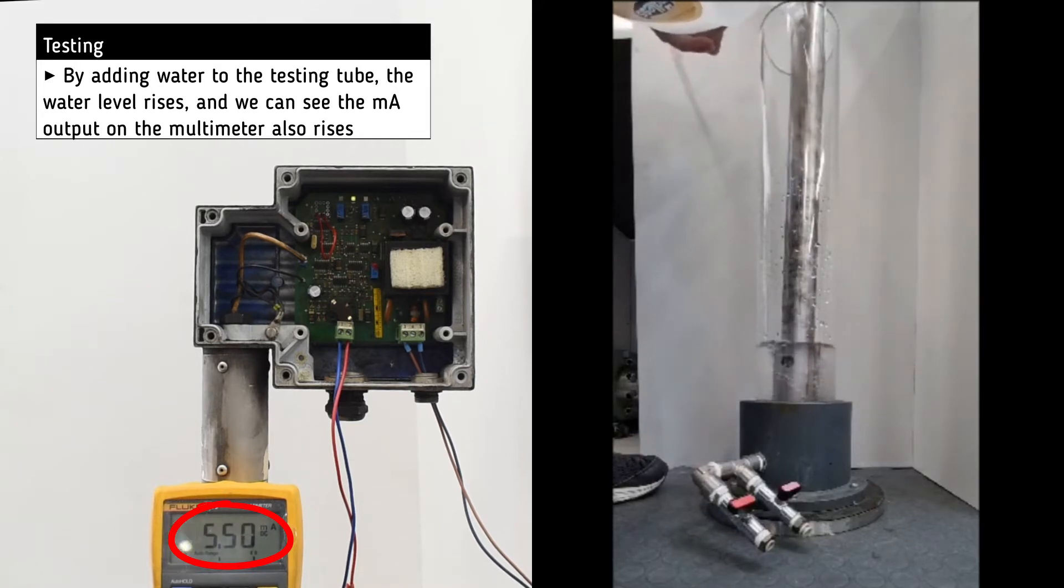we add water and as the water level rises, we can see the milliamp output also rises as shown on the multimeter screen.